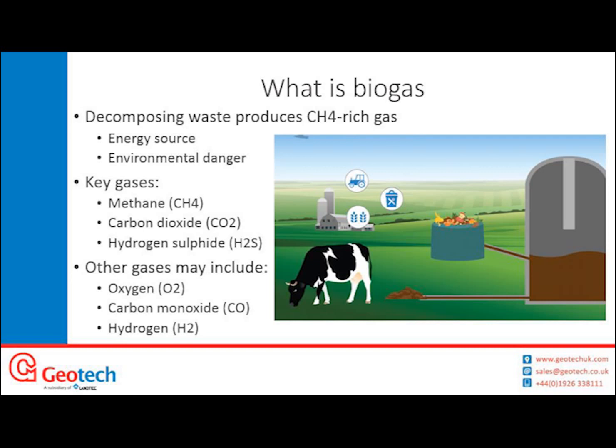Methane is essentially the fuel. Carbon dioxide is important for the anaerobic process, and hydrogen sulphide is a gas we need to monitor because it is damaging to the equipment on site, for instance your engine or CHP. Other gases that are included are oxygen, carbon monoxide and hydrogen.